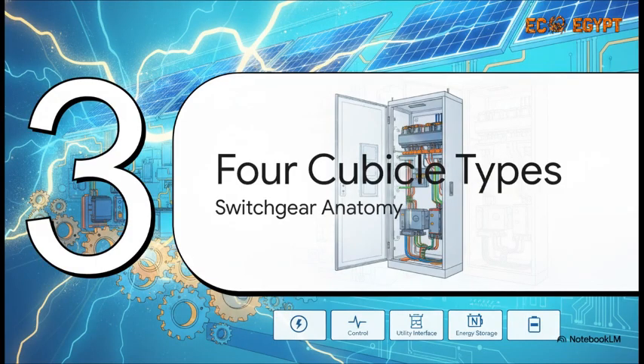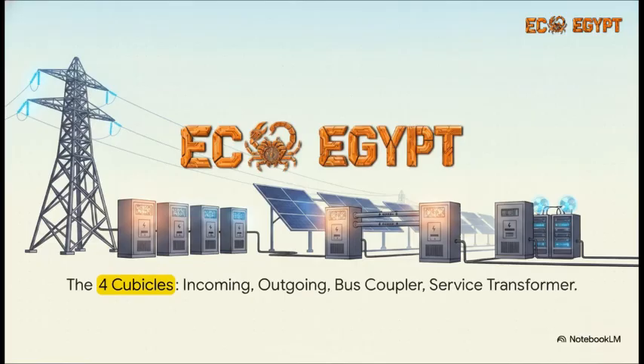Section 3. The 4 cubicle types: anatomy of the switchgear. When we break down the anatomy, this system is actually highly modular. There are 4 primary types of cubicles, or organs if we stick to our nervous system metaphor. First, you have the incoming cubicle, which serves as the main grid feeder. Second are the outgoing cubicles. These are your PV feeders bringing power from the inverter transformers straight to the MV bus. Third up is the bus coupler, which is a vital link connecting bus A to bus B. And fourth is the service transformer cubicle. This one steps power down to feed the auxiliary low-voltage loads. Think things like cooling fans and the SCADA servers themselves.